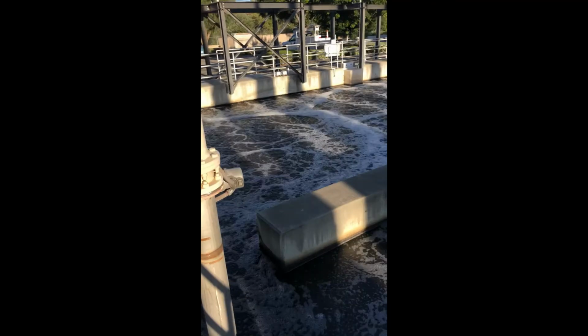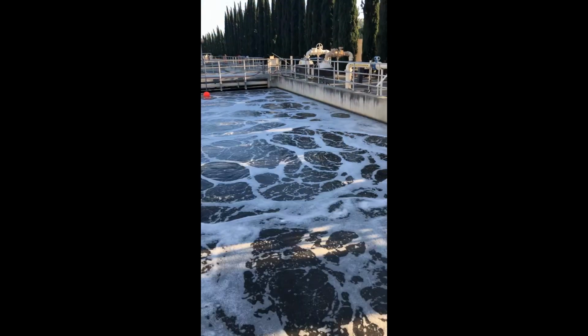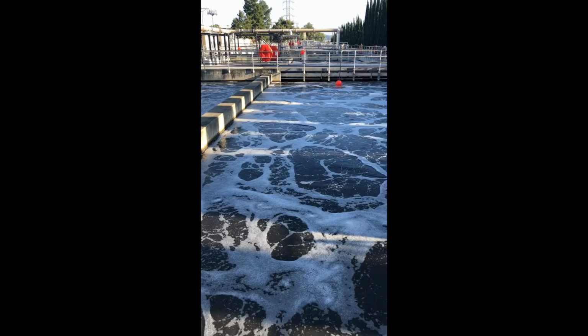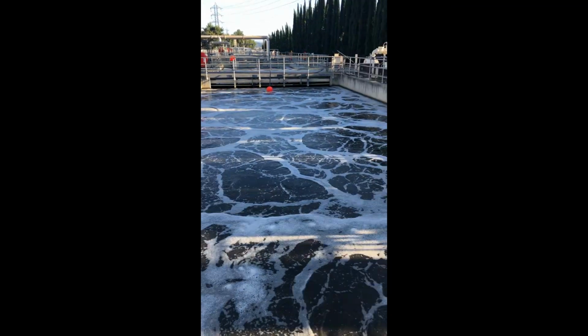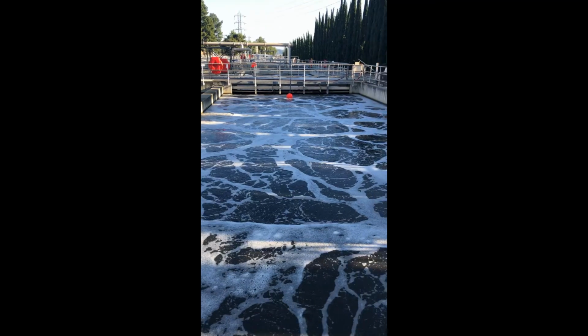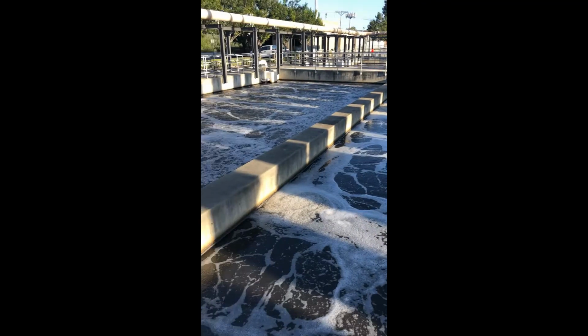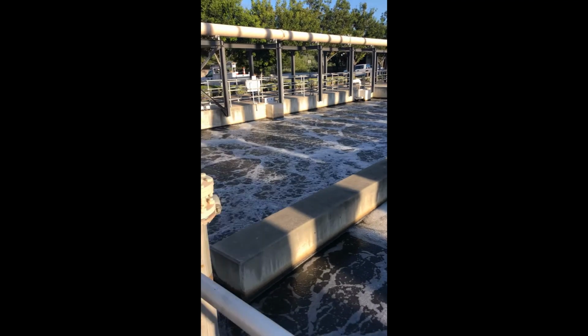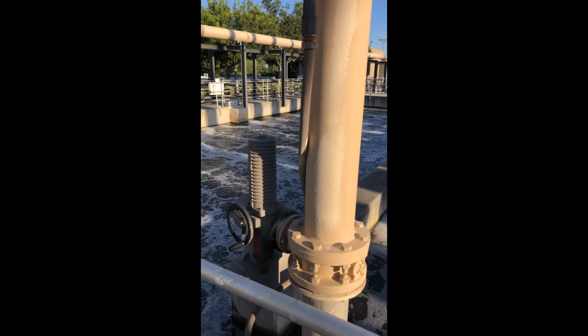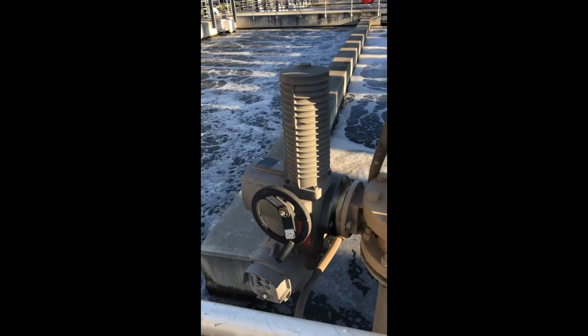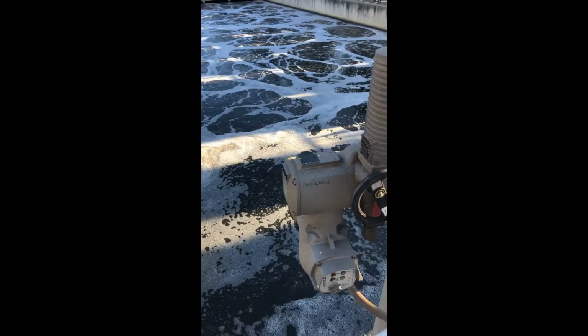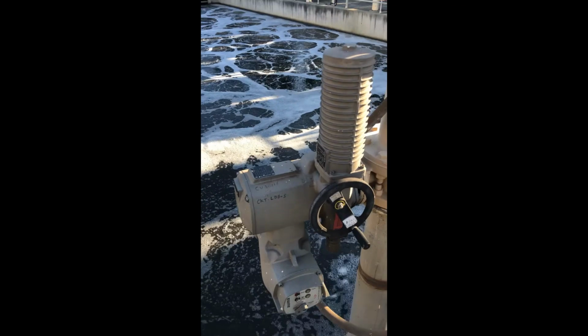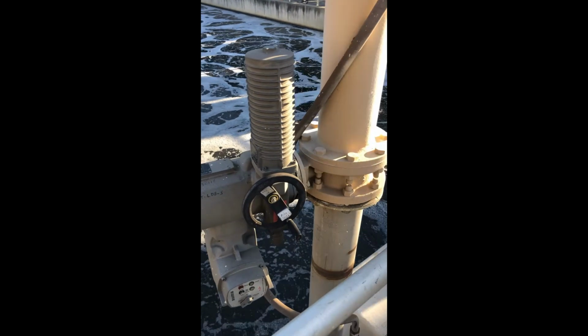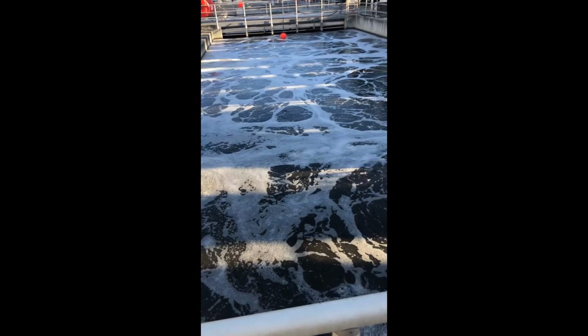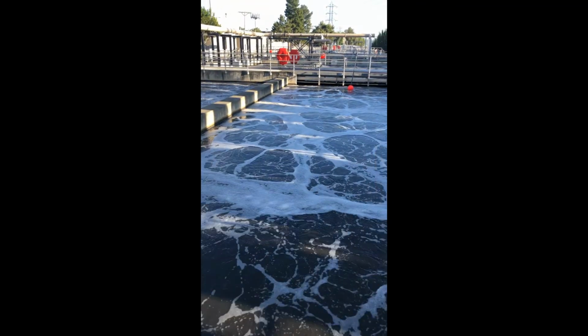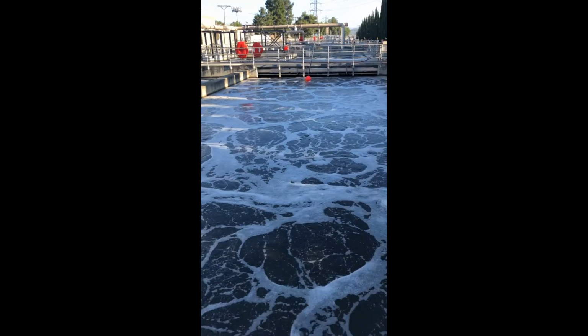And in these 2 tanks, they can control the amount of dissolved oxygen, so it's ideal. They want just the right amount of oxygen. Too much is not good and not enough is not good, and that's about all I really know about that. It gets complicated, and that's more of the operator expertise, but controlling the amount of air is a closed loop control. This is the motorized valve that will open and close depending on how much dissolved oxygen is in the tank and what the set point is from the operator, okay?